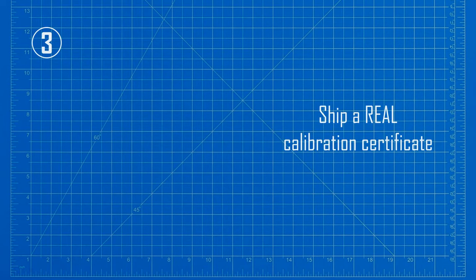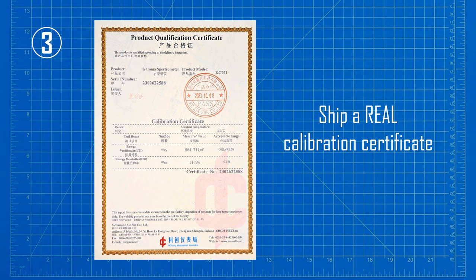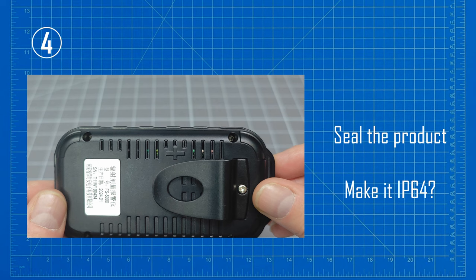The next suggestion is just a minor point: if you want this product to be taken seriously as a professional instrument, it needs to be calibrated on the production line and supplied with a certificate showing this calibration value. I have worked on projects in quite literally hundreds of Chinese factories, and I know exactly what the actual value of this piece of paper is — it literally means nothing. This is what a real calibration certificate looks like. My next suggestion relates to the holes in the back of the device for the GM tube: these should be covered over, perhaps with a thin metalized Mylar sheet, to prevent contamination and also create a nice visual feature. If the sound port had a waterproof mesh and an o-ring was added between the two halves of the casing, this device could probably be rated as having some level of waterproofing.